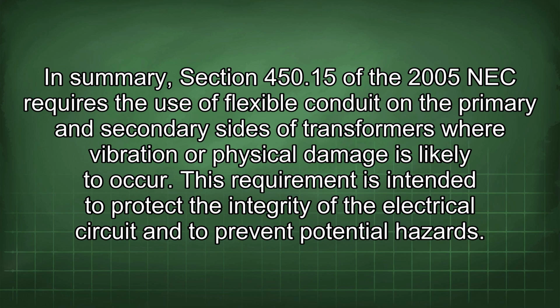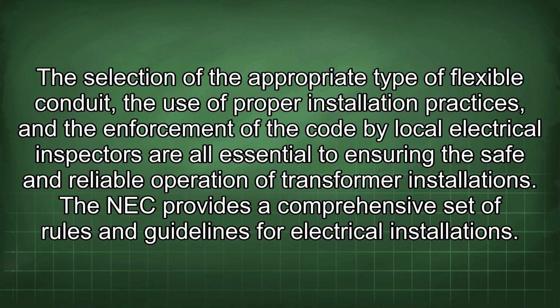of transformers where vibration or physical damage is likely to occur. This requirement is intended to protect the integrity of the electrical circuit and to prevent potential hazards. The selection of the appropriate type of flexible conduit, the use of proper installation practices, and the enforcement of the code by local electrical inspectors are all essential to ensuring the safe and reliable operation of transformer installations.